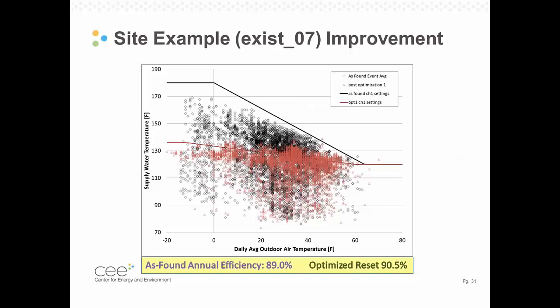And so we did this at Site 7. What you see here is that supply outdoor reset curve. The black line that you see on this plot is very similar to that example I walked you through in the manufacturer default, which was what we found when we walked into the home. And then the red line is the curve that we adjusted during our optimization. And each individual point on this curve is a single heating cycle at this home.